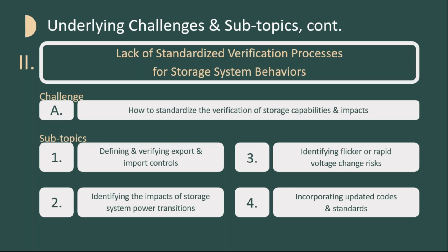That relates to how a utility would evaluate those impacts on the distribution system. Right now they're probably scouring spec sheets, sometimes even contacting manufacturers to get the data they need. So it may be useful to have more standardized ways of verifying how storage systems transition between power levels — not just charge to discharge, but also the ramp rates between two output levels, since they can change very quickly.